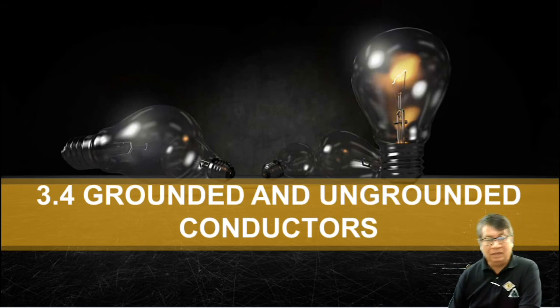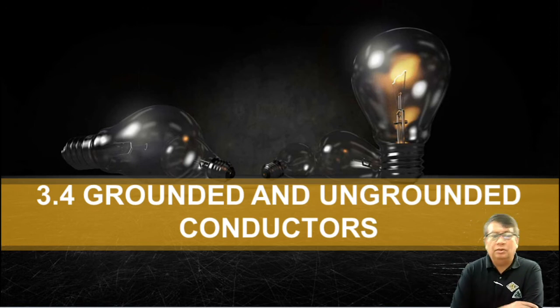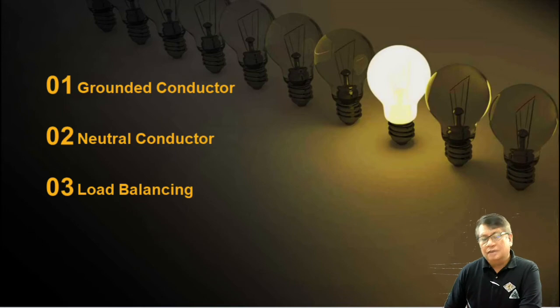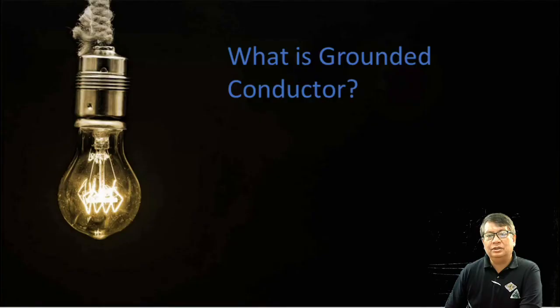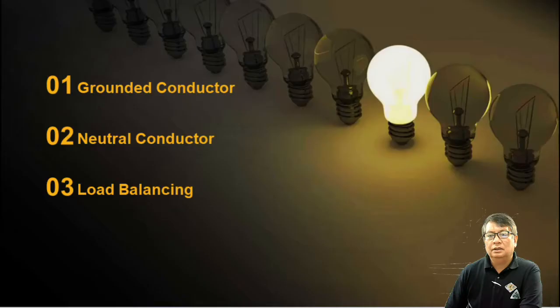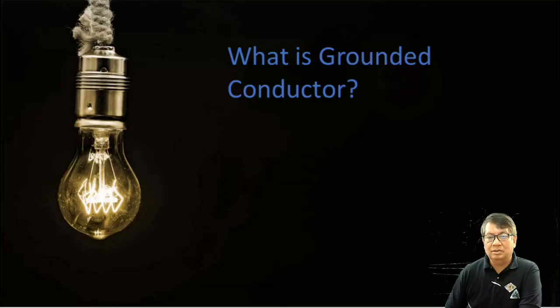Okay, so 3.4. This is all about grounded and ungrounded conductors. So let's proceed to 3.4, grounded and ungrounded conductors. We have here some of the content: grounded conductor, neutral conductor, and the load balancing. We are going to discuss this one by one. What is the difference between a grounded conductor and neutral? And of course, load balancing.